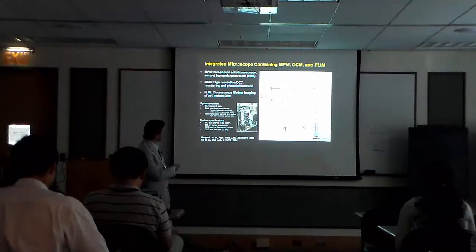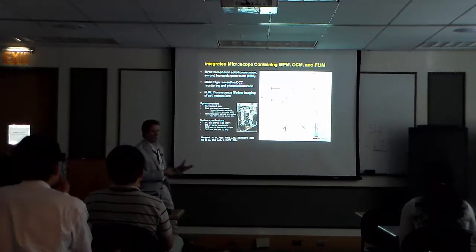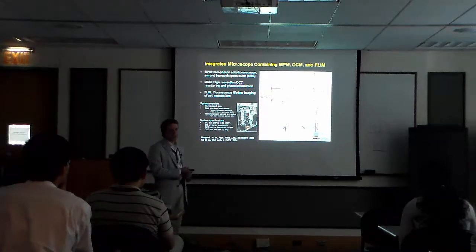The physical acquisition, as we'll see in this case, maybe I can show you, we have our optical source, but we have different detector arms. Here's our sample, which is going to produce fluorescence or backscattered light. Our fluorescence is picked off and we can send some to our FLIM. We have multiple PMTs for the SHG signal or other signals. Our OCT signal comes back here to an interferometer to collect scattering or phase information. So we have different detectors, all collected at the same time, and so we have separate data sets.